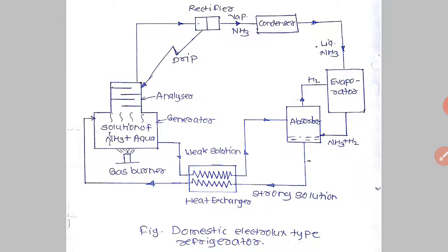Why? Because there are three fluids used in this system. The main purpose of this system is to eliminate moving parts, that is, we have to eliminate the pump here, so the system will be noiseless. The three fluids are ammonia, hydrogen and water. The ammonia is used as refrigerant because it has the most desirable property. Ammonia is toxic, but because of the absence of moving parts there will be no chance or little chance of leakage. So the amount of refrigerant will be small.